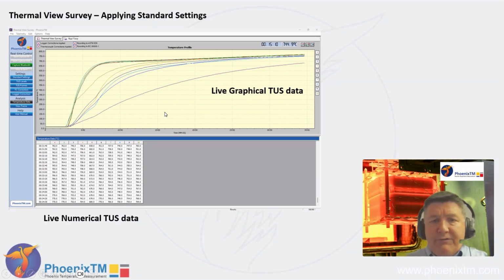Whether using RF telemetry or USB hardwired connection, once the system is running, you would go to the real-time tab and you can then see both graphically and numerically the data that's coming back from your data logger to the computer screen. You can then see where your temperatures are in the furnace, whether you've achieved your TUS level, whether you're within specification, and I'll talk about this later on, where you can apply the TUS levels to see whether you are in spec, but that's in a later video. But at the end of the day, you can see everything that's coming out of your furnace live on screen.